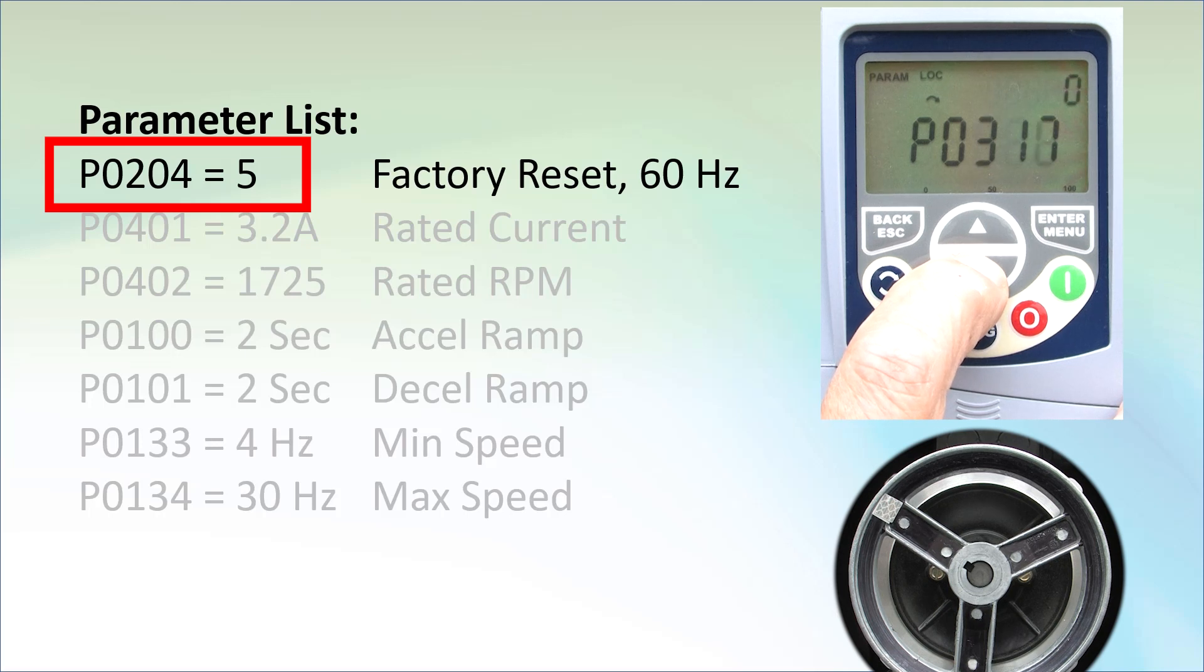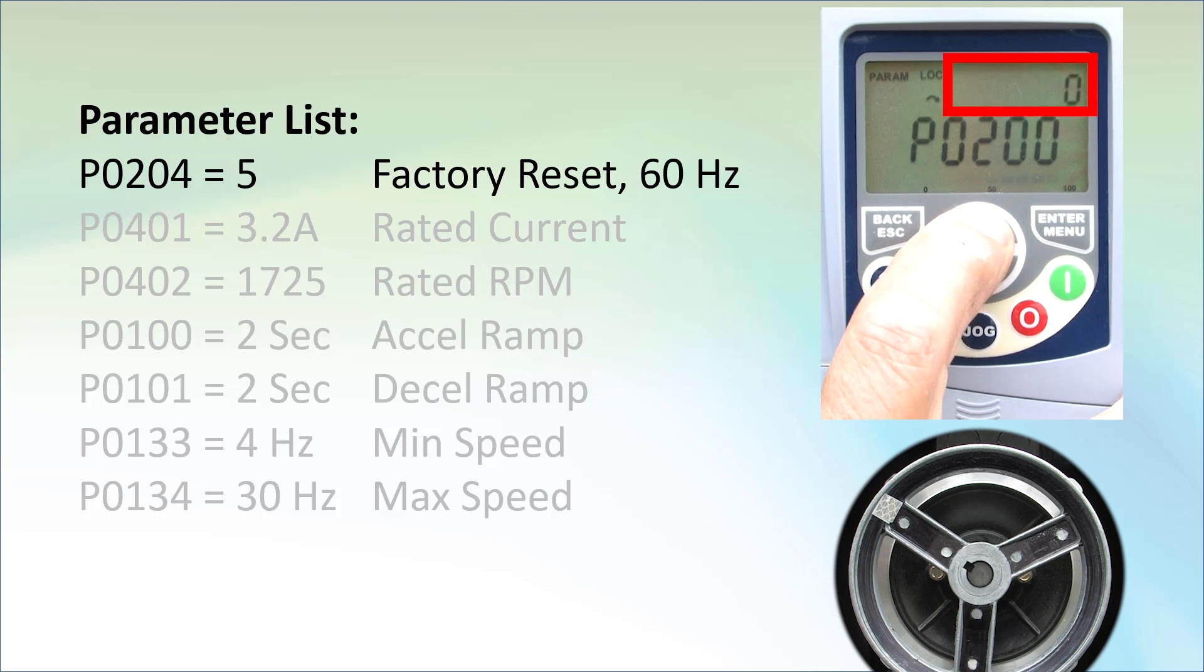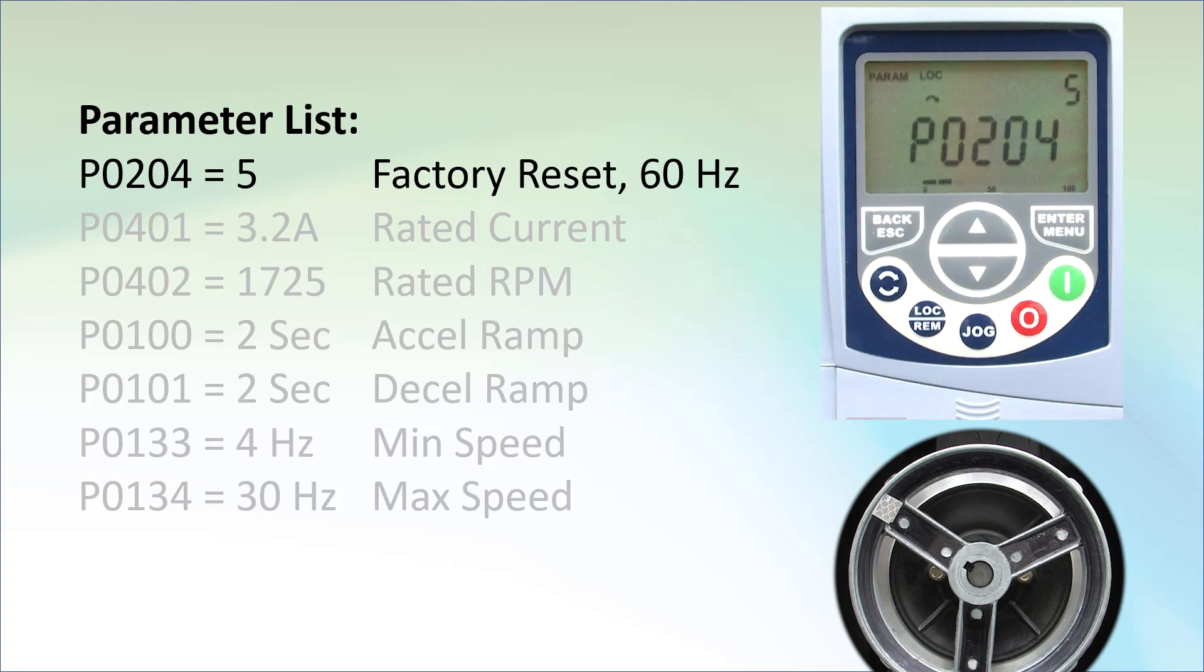Scroll to parameter 204. The value of each parameter is displayed up here which makes it super quick and easy to see what's in each parameter. Press enter and change it to a 5 to reset the drive to 60Hz operation. The bar graph shows you the progress and when it's done, the drive restarts.